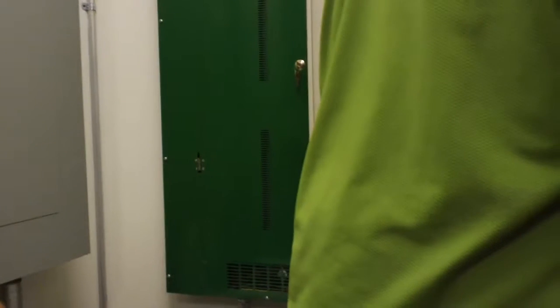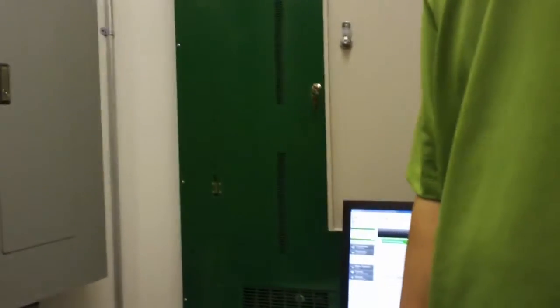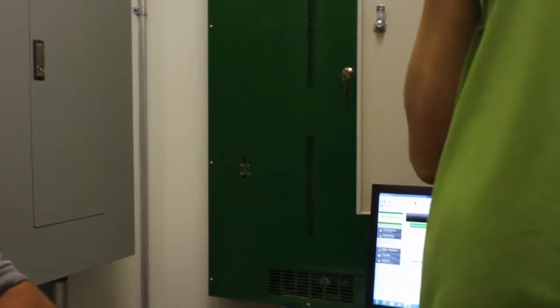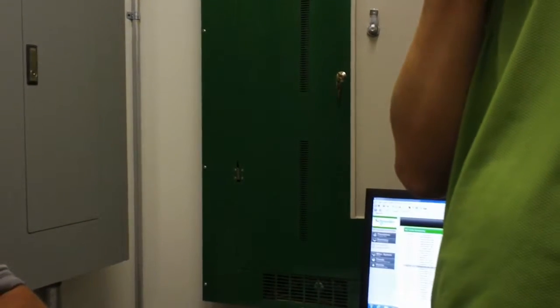That's correct, the indoor blower motor turns off to heat up the heat exchanger first. Okay. Then your indoor blower motor comes on. Why are you getting an alarm or something? It's an alarm. I got lots of alarms. So you're going to have to put a delay on there because what's going to happen is every time it goes for call for heat, it's going to turn on the inducer fan motor, heat up the heat exchanger, then the indoor blower motor is going to come on.